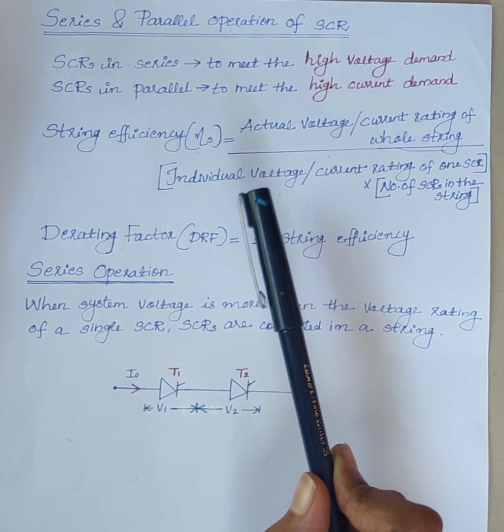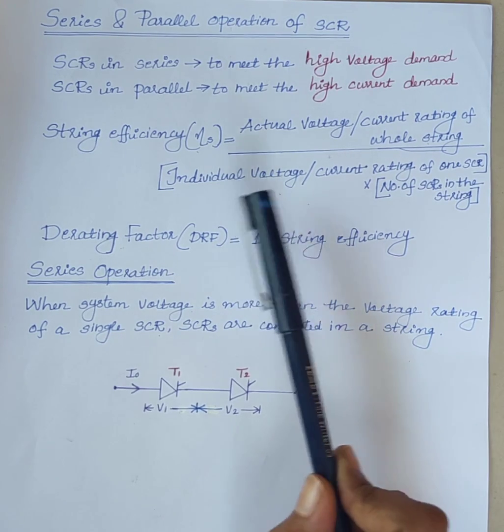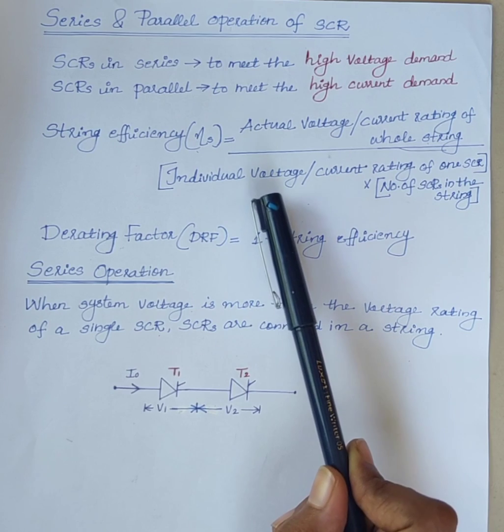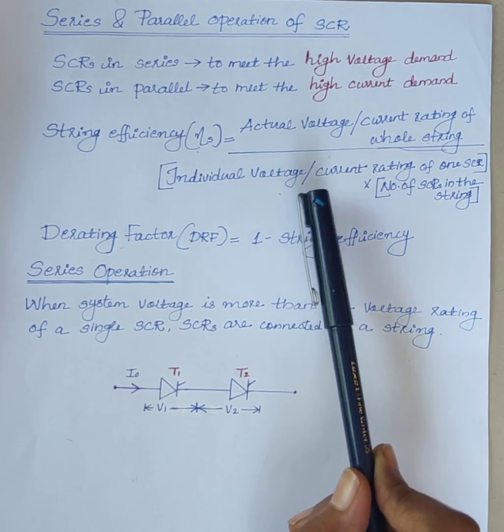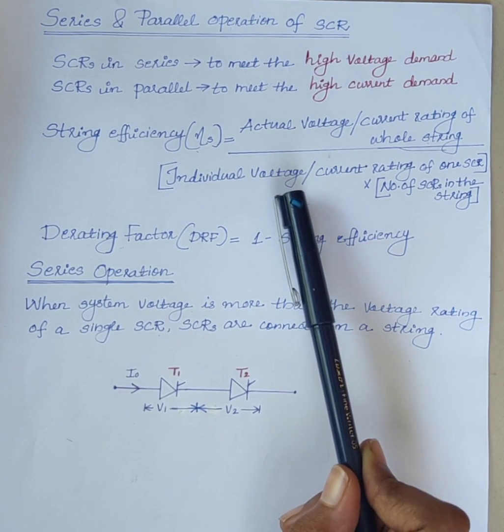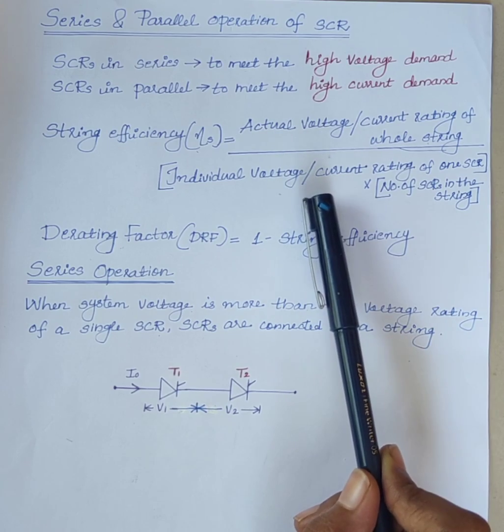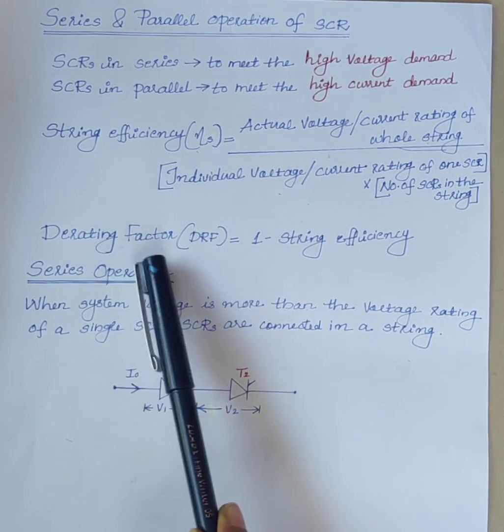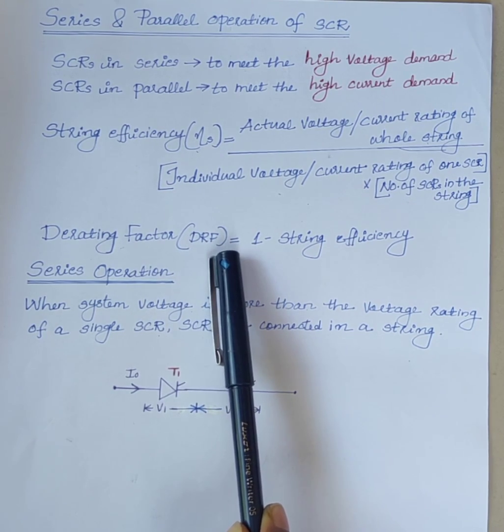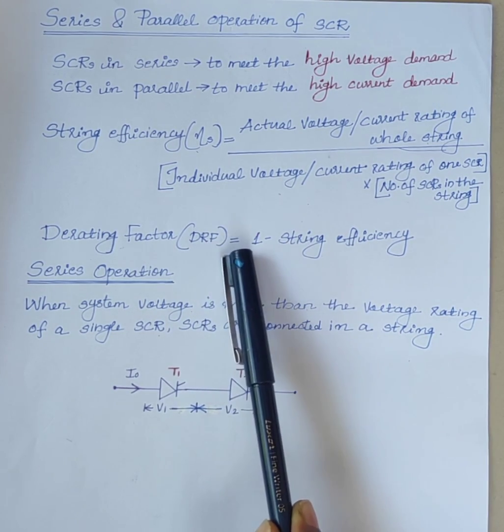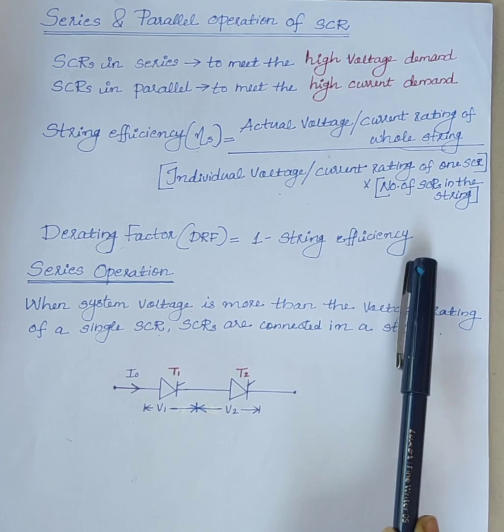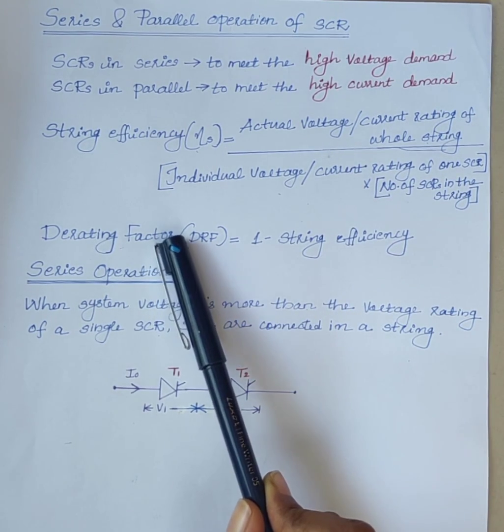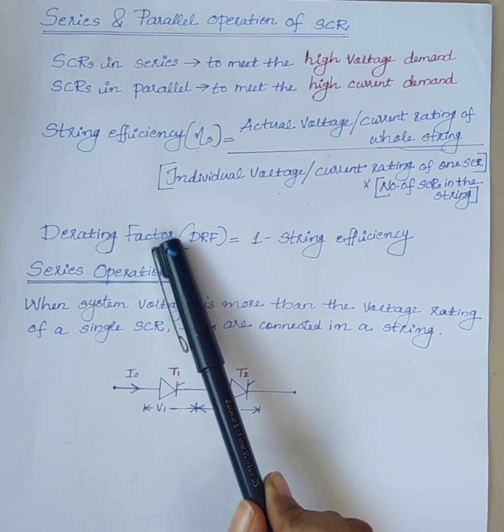This phenomenon increases the reliability of the string but reduces the utilization of each SCR. The measure of reliability of the string is given by a factor called derating factor. derating factor is equal to 1 minus string efficiency, and it is used to measure the reliability of the string.